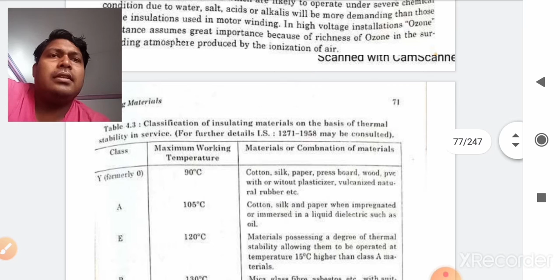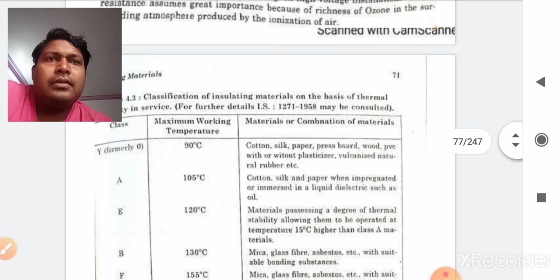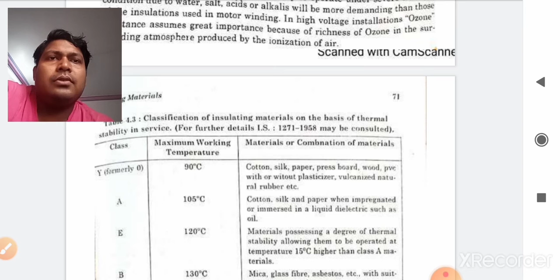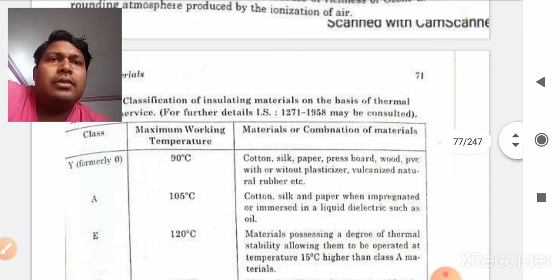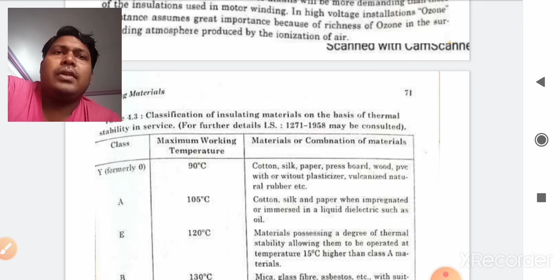So there are different classes of insulator. They can be classified as Y, formerly O. Earlier they were known as O type or class O. Now they are known as Y class or class Y. The maximum or working temperature here is 90 degrees, and the materials used for this kind of insulator are cotton, silk, paper, pressboard, wood, PVC, with or without plasticizer, and vulcanized natural rubber. So vulcanized natural rubber is also another resource which is used for insulating material for class Y. You have to remember these classes, mind you students.